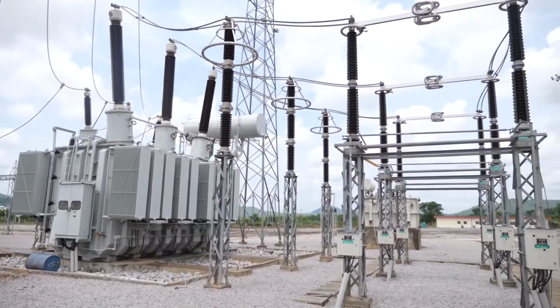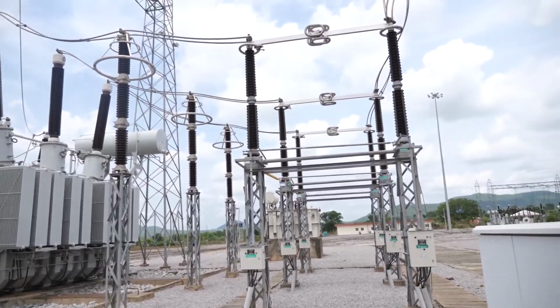Or maybe the fans of the transformers are not working, and you find out that the transformer is loaded. Then you check the MCB that is controlling that fan and reset it. Also in the battery bank, in the course of inspection, maybe the air extractor is not on, you put it on. So those are the routine maintenance we do here.